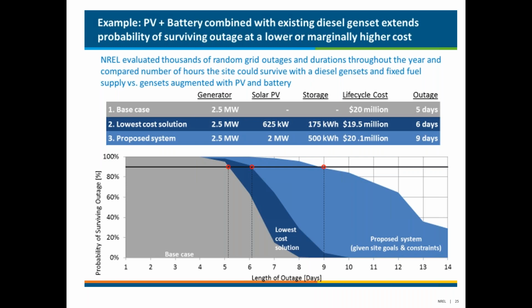But it helped extend the probability of having power from 7 and 8 days to 14 days, as you can see in the graph at the bottom. This extension in survivability occurs because the PV and battery system can extend the useful lifetime of the diesel fuel, using solar energy when available to store it in the battery system, and reducing the need to use diesel fuel for the total duration of the outage. Those first 7 days of an outage can be really beneficial. So this takes a conventional diesel system and combines PV and battery to show what the survivability might look like.